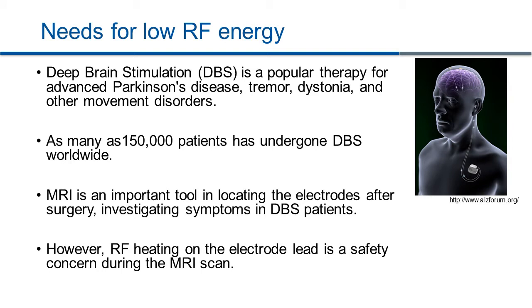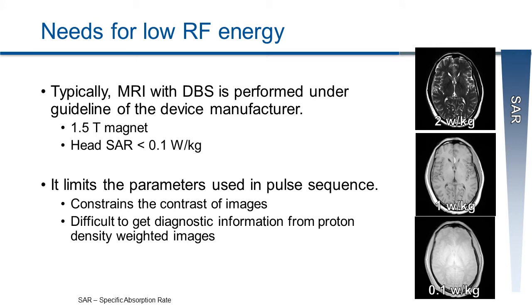There are many reasons to reduce the RF energy in MR scans. Here I use Deep Brain Stimulation (DBS) as an example. DBS is a popular therapy for advanced Parkinson's disease or other movement disorders and is getting more and more popular. MR is an important tool in locating electrodes after surgery and investigating symptoms in patients implanted with DBS. However, RF heating on the leads is a safety concern during MR scans. Typically, DBS manufacturers suggest using SAR less than 0.1 watts per kilogram to scan patients with the device at 1.5 tesla.